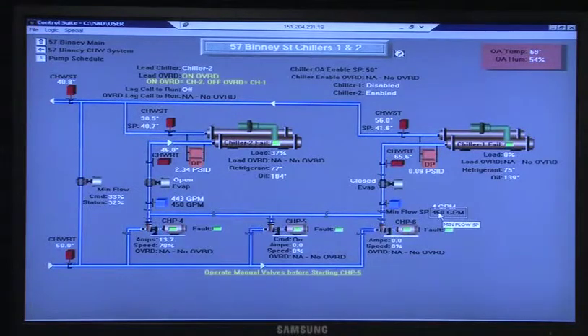Just to remember what it's called, this is minimum flow. You can send 500, 600 through these. It doesn't like to go lower than that. Is there a chance of freezing? Exactly, you have a potential, yes. It's not as efficient either. Icing out is not good. They want to keep the flow through the bundle.